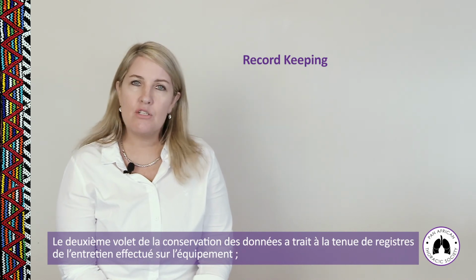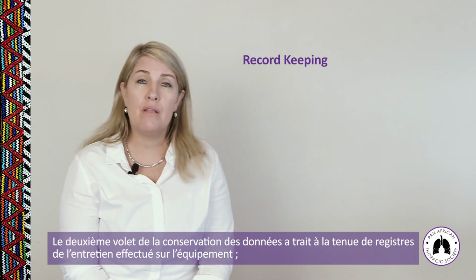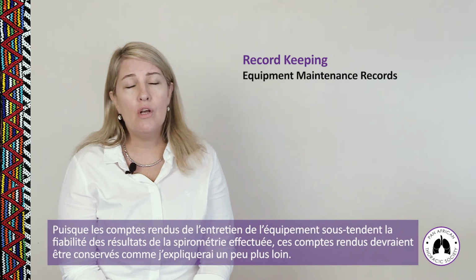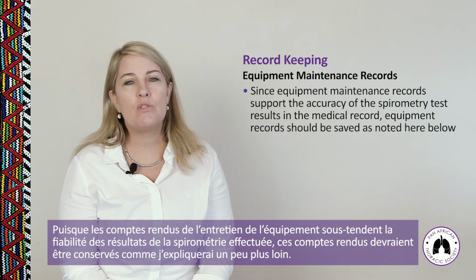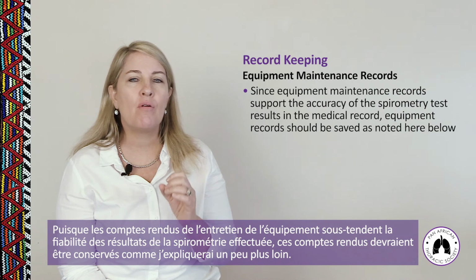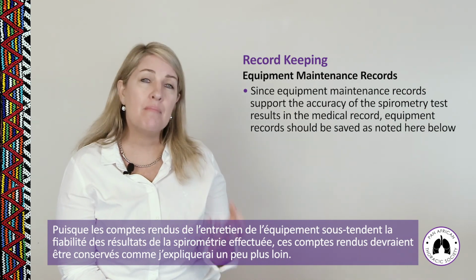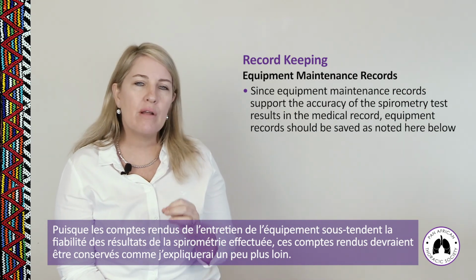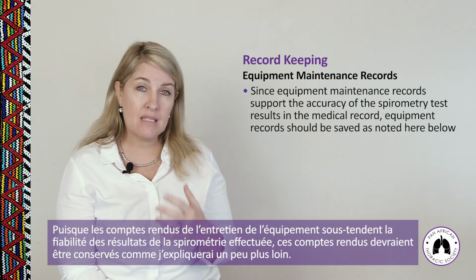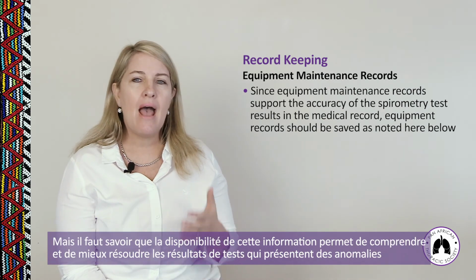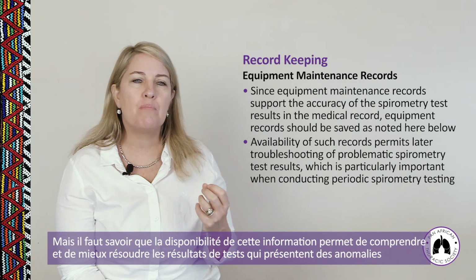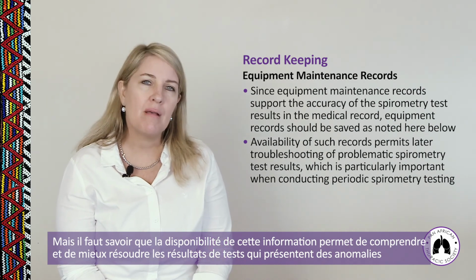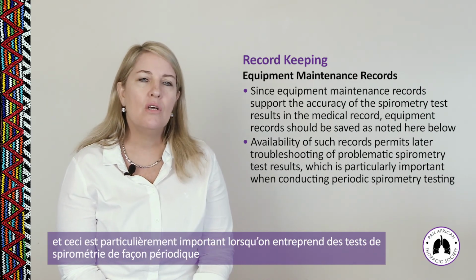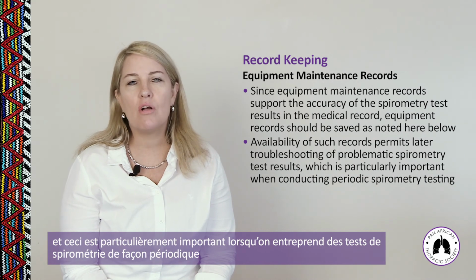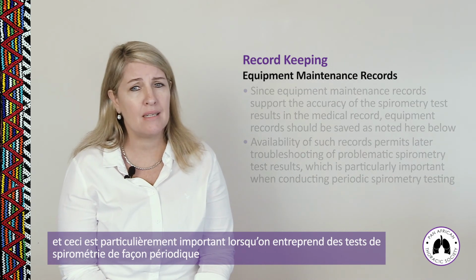The second aspect of record keeping has to do with equipment maintenance records. Since equipment maintenance records support the accuracy of the spirometry test result in the medical record, these records should be saved, as I'll explain shortly. Their availability permits later troubleshooting of problematic spirometry test results, which is particularly important when conducting periodic spirometry testing.